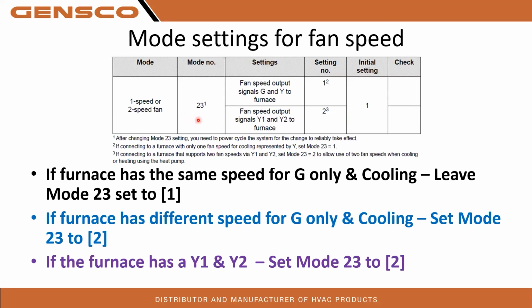Mode 23, which is normally in your MHK2 manuals and stuff, is going to be for your auxiliary heater control during emergency operation. On this setup, it is going to be selection of either one-speed or two-speed fans. So single stage versus two-stage furnace. So again, make sure to read your manuals on these things and the Intelli-Heat coil of what your modes are.